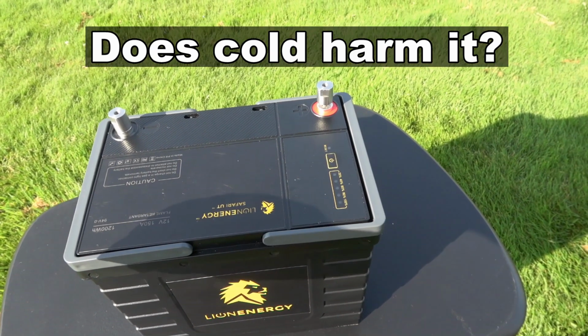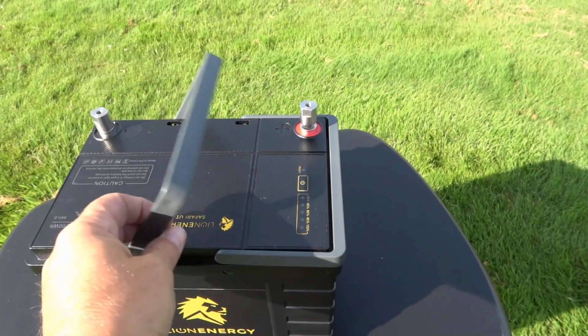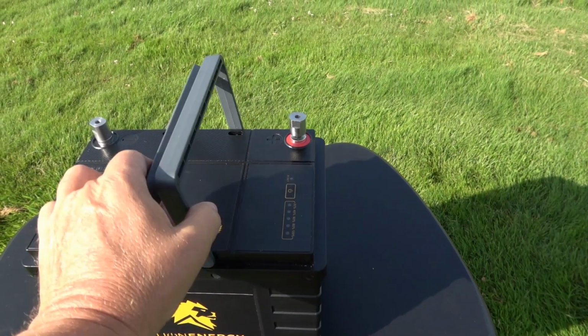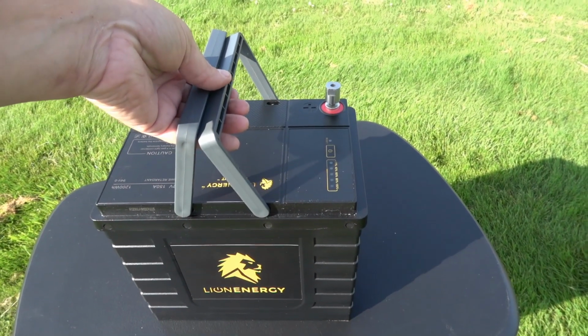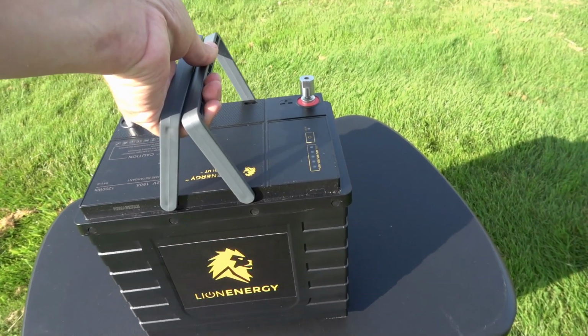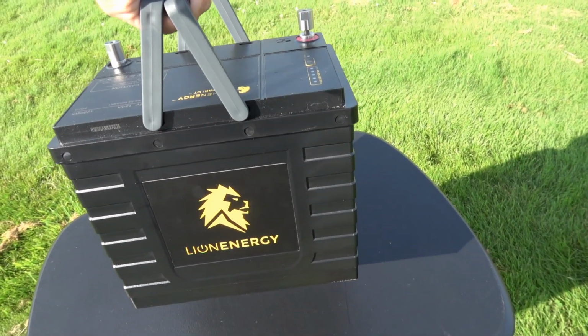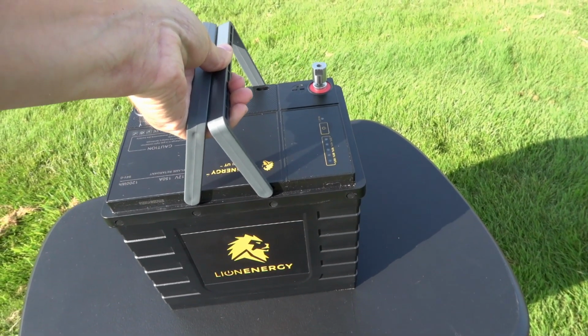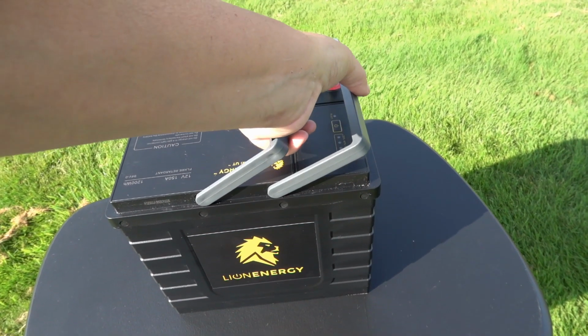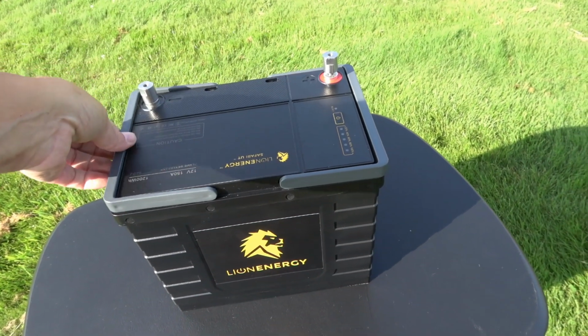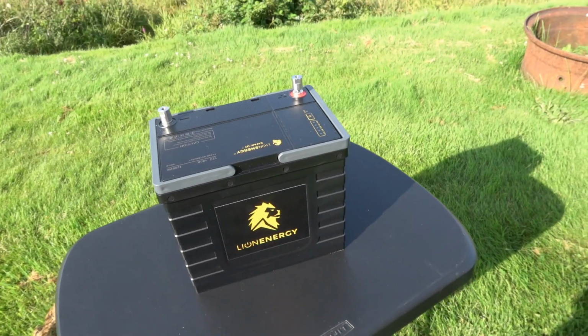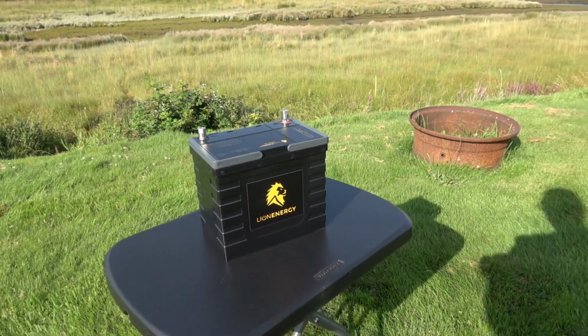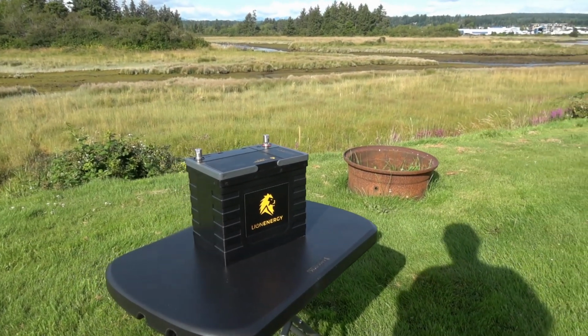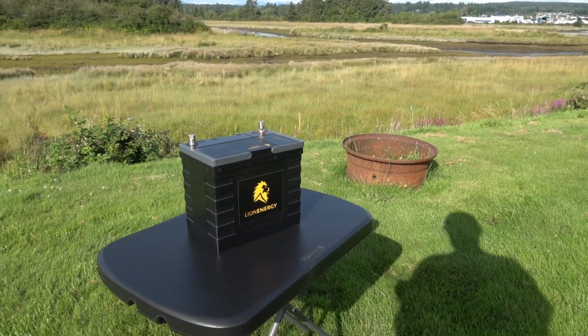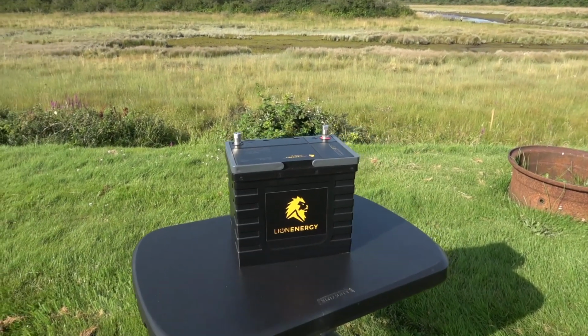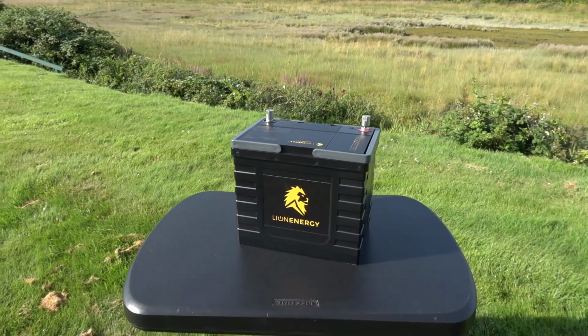Does letting the battery get too cold harm it? The lithium iron phosphate cells inside shouldn't be charged below 32 degrees Fahrenheit (0 Celsius), or discharged below -4 Fahrenheit (-20 Celsius). But the BMS inside the Safari will automatically shut down charging and discharging before these limits are crossed, protecting the battery cells from damage. So because of that BMS, you don't have to worry about damaging your cells - it just means if you're trying to charge your batteries, they won't charge once it gets below freezing, and they won't discharge once it gets below -4 Fahrenheit or -20 Celsius.